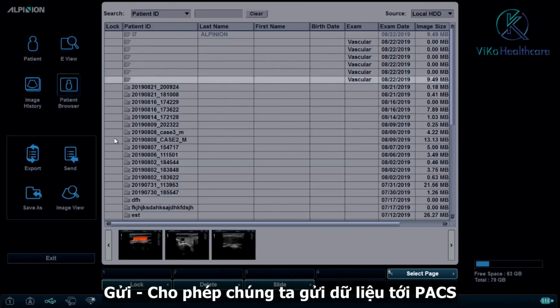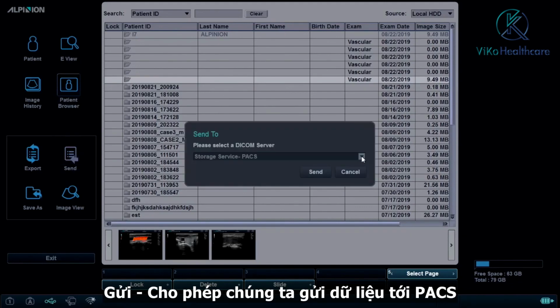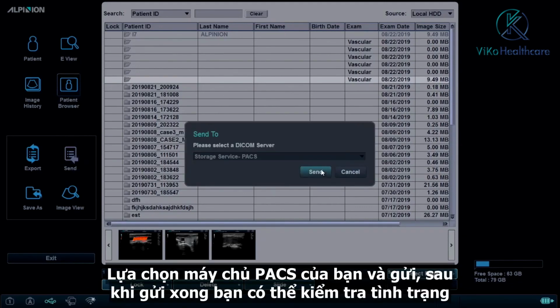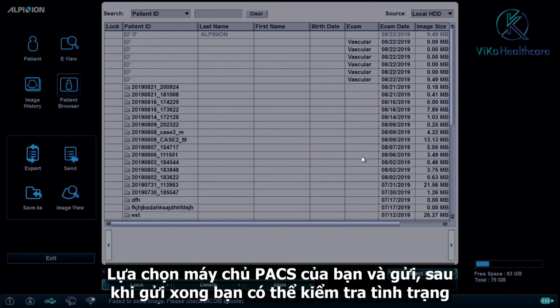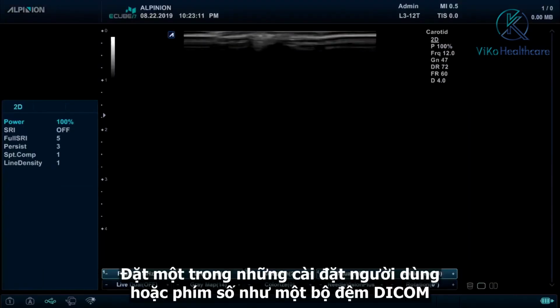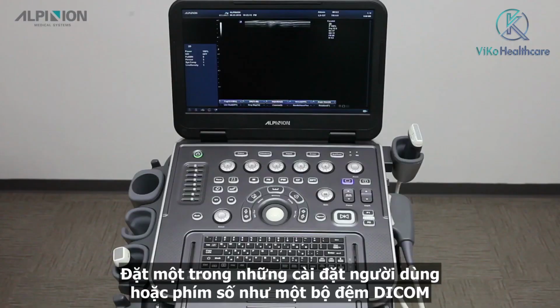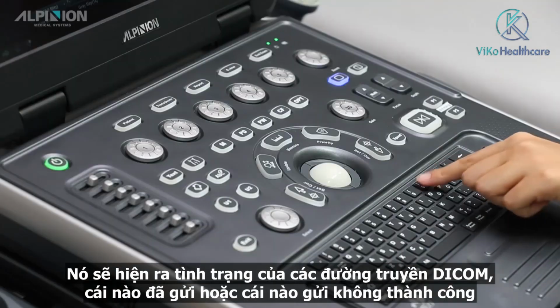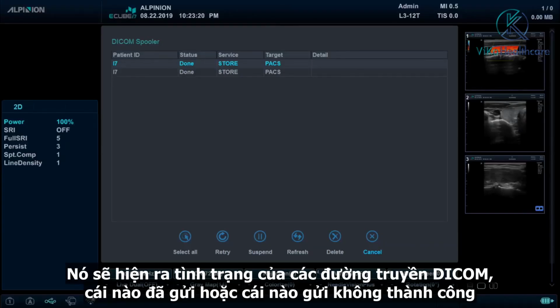Send. This allows us to send data to PACS. Select your PACS server and send. After sending, you can check the status. Set one of our user-defined or numeric keys as DICOM spooler. It displays status of all DICOM transfers which have been sent or which have failed.